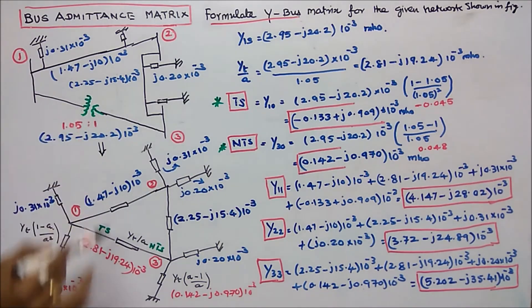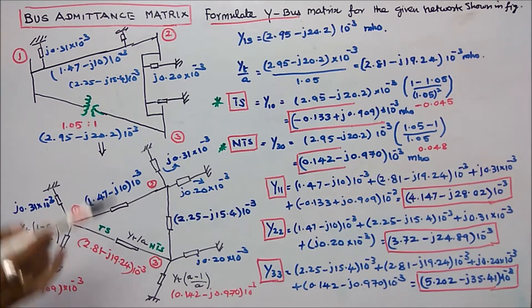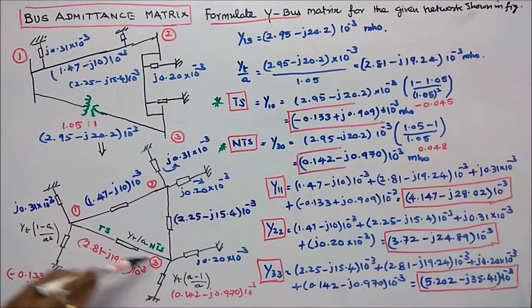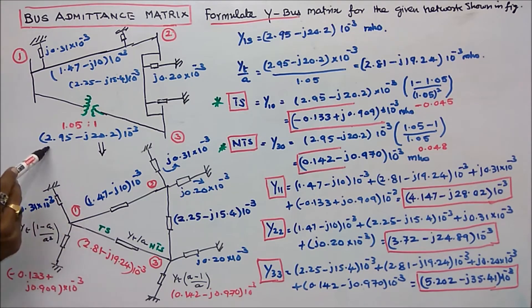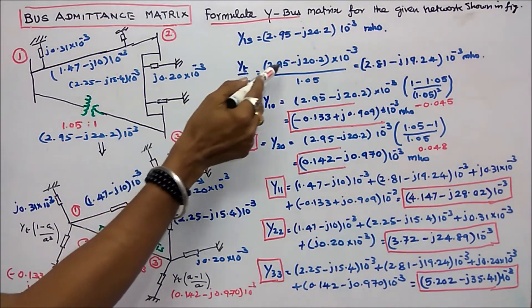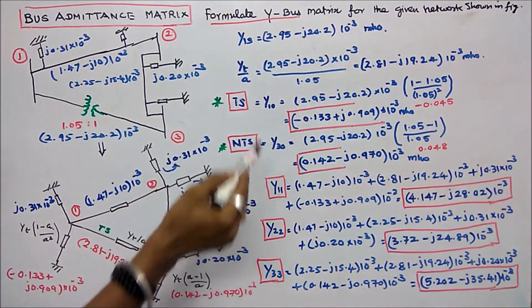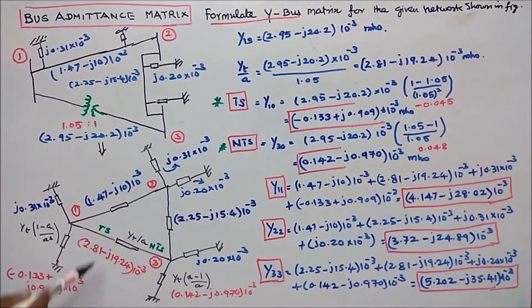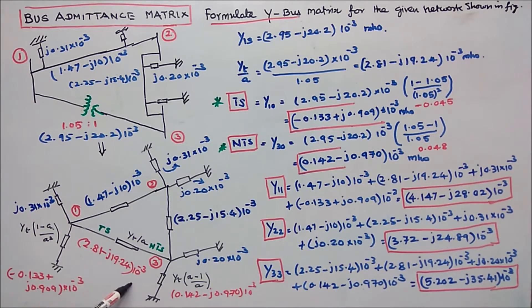The first step is to draw the equivalent circuit and mark all the admittance values. When the transformer is included in line 1-3, this admittance is yt divided by a. Here yt equals 2.95 minus j20.2 into 10 power minus 3. Dividing by a equal to 1.05, this admittance becomes 2.81 minus j19.24 into 10 power minus 3.